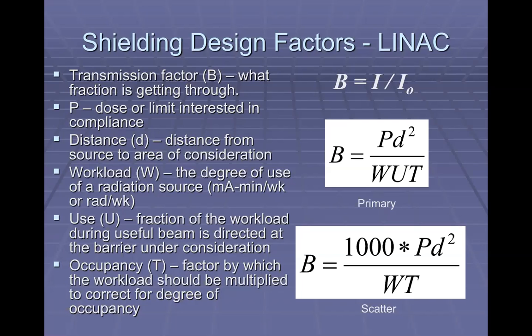So that's going to be, again, a very important factor in figuring out how much you need to shield, because you need to know how much radiation is actually coming out of the machine. If it's on all day, every day, that's a big difference than a couple of minutes of beam on time a week or a day.